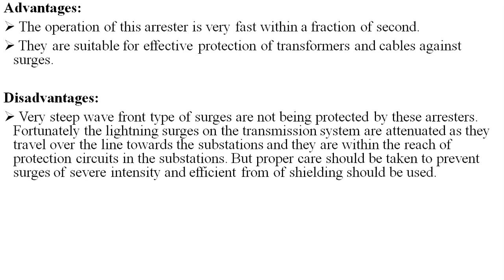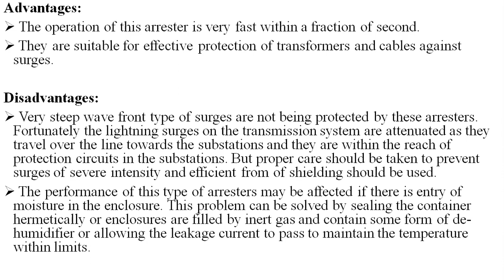The performance of this type of arrestor may be affected if there is an entry of moisture in the enclosure. This problem can be solved by sealing the container hermetically, or the enclosures are filled with inert gas and contain some form of dehumidifier, or by allowing the leakage current to pass to maintain the temperature within limits.